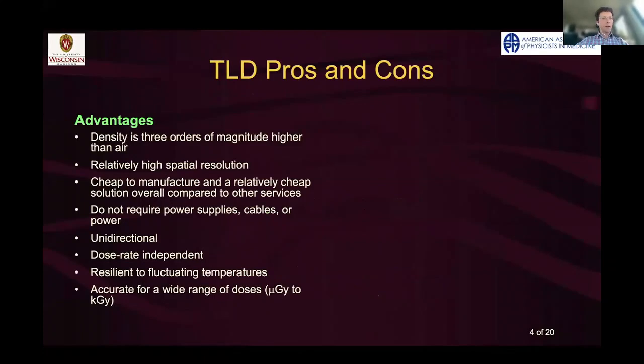So on this slide, I'm going to go through some advantages and disadvantages of using TLDs for in vivo dosimetry. An advantage is the density is 3 orders of magnitude higher than air. So it's a whole lot better than an ion chamber for this type of dosimetry. And because it has a high density, it has a very high spatial resolution. You can get TLDs that are very, very small. In fact, probably smaller than you want to work with. So you choose sort of a medium-sized TLD for in vivo dosimetry.